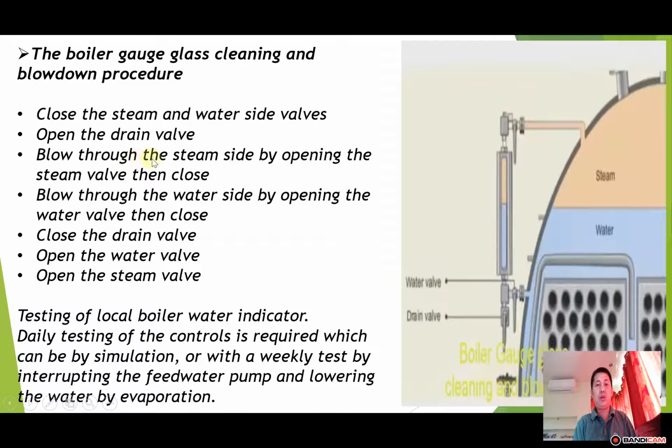Blow through the steam side by opening the steam valve then close. So this is already open and this is closed. So you have to open this one, open and close again. Blow through the water side by opening the water valve then close. So open this for 20 seconds and close. So the same with this one.